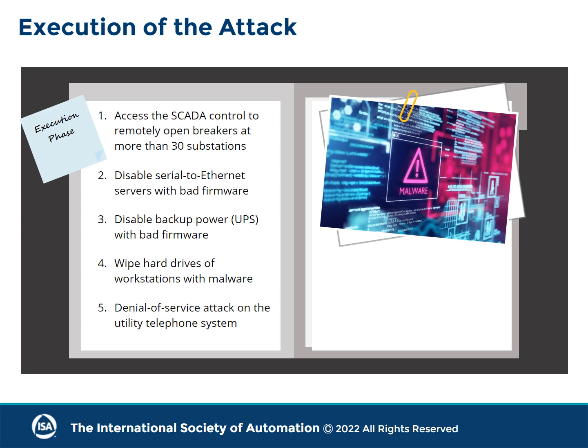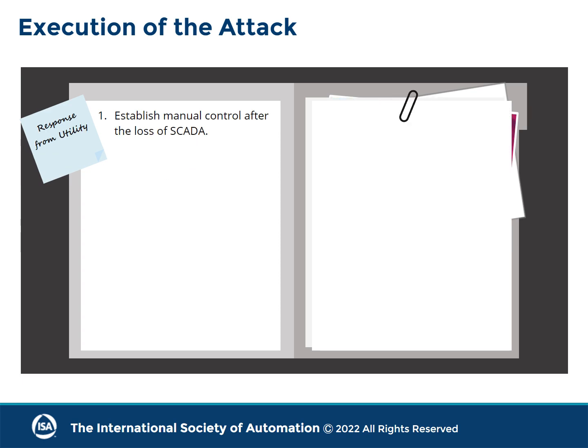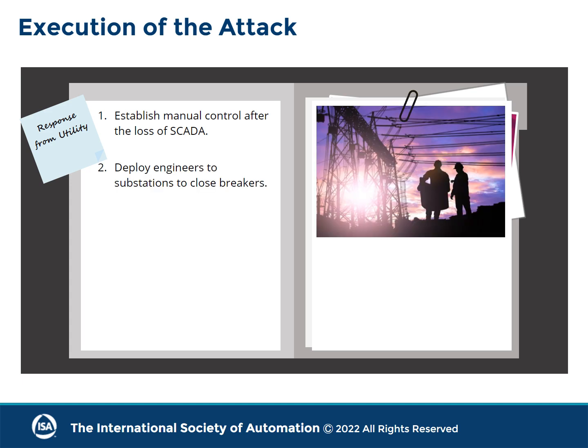It also further complicated the operator's situational awareness—they couldn't get information from their customers. The power utility responded by going to manual control after the loss of their SCADA systems, and engineers had to get into trucks and travel out to the affected substations to close the breakers, and power was restored.